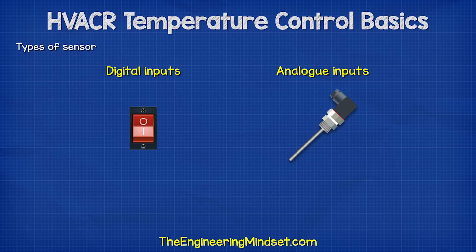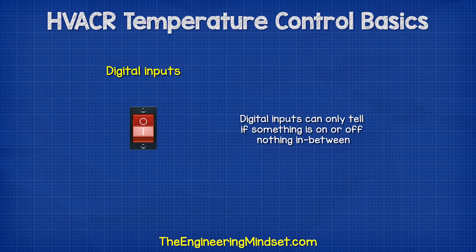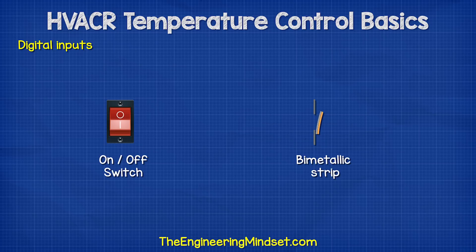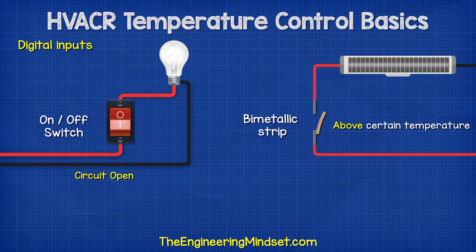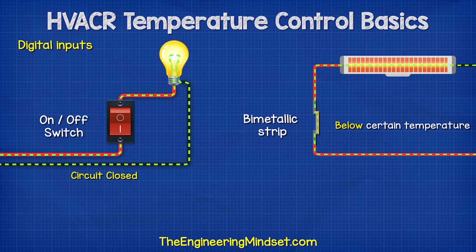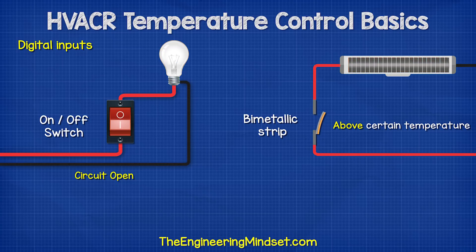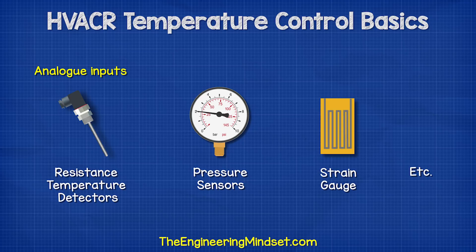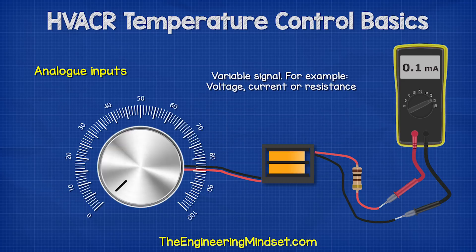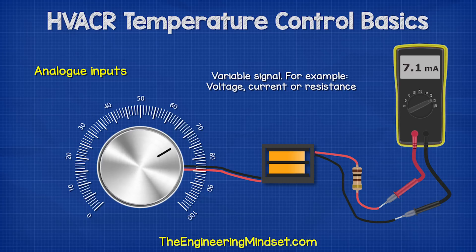We have two main types of sensors: digital and analog. Digital inputs can only tell if something is on or off — nothing in between. For example, an on-off switch or a bimetallic strip. The circuit is either open or closed, so we can only tell if the temperature is above or below a certain temperature. Analog inputs vary their signal — they might vary in resistance, voltage, or current between a minimum and maximum value. So we can use these to determine the exact temperature or pressure.